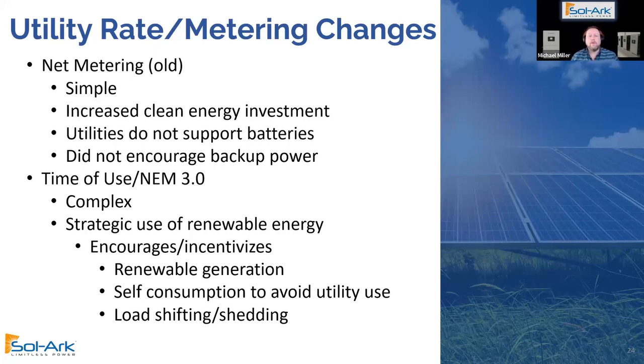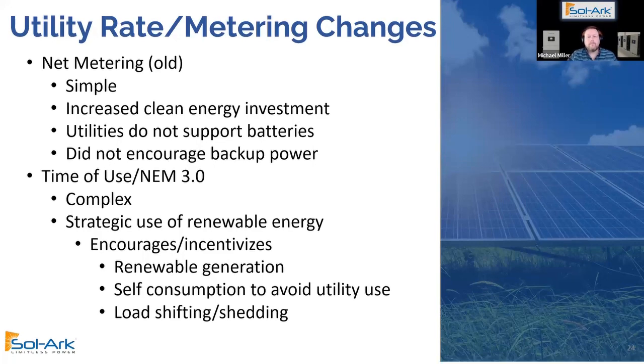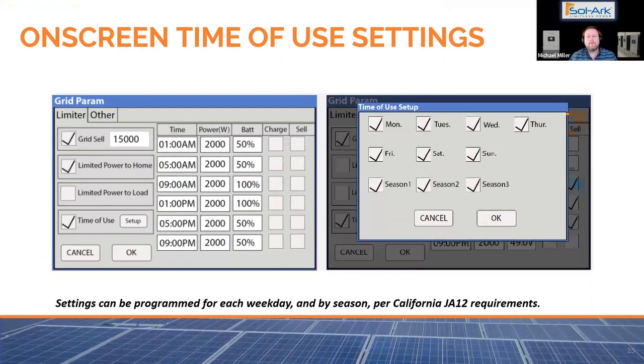As we move forward, we know things are getting more complex. We know that, for example, in NEM 3.0, I'm going to do a quick example with that. We are looking at more strategic use and timing of these resources. So be prepared to get your time of use settings down, and I'm going to teach you a little bit more about how Sol-Ark does that. This is our basic time of use screen on our inverters. Go right up to the inverter and program it. In the top left here, we have the grid sell ability. You can have that on or off. We have limited power to home and limited power to load. Essentially, that means either you're using the CTs if it's, say, a partial home and you want to limit the entire home to try to use the batteries and the solar the best it can to limit the total usage of the grid.